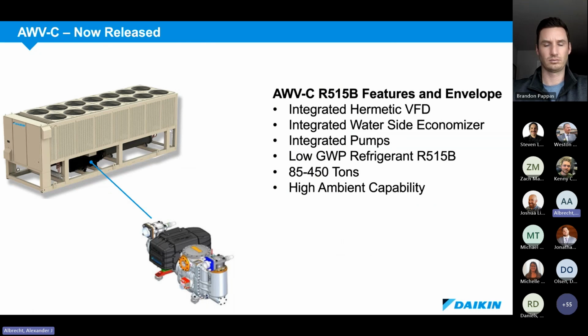Now, as mentioned, those are the product offerings as they are today. But looking ahead, for this slide, we have our latest release, which we've just released. It's our new vintage AWVC with R515B low GWP refrigerant. And with that low GWP refrigerant, 515B also allows for low pressure ratio operation. And for this new design, it comes with an integrated VFD, which is refrigerant cooled, all of which allow us to operate at real high ambient temperatures, which is generally ideal and of high demand for process cooling, such as the data center market.